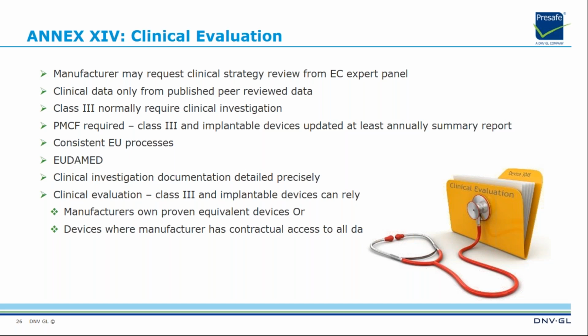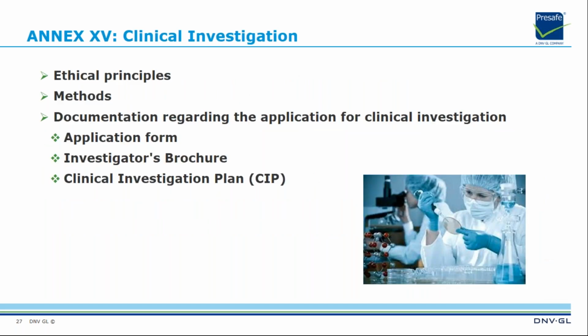evaluation reports, if not reviewed within the last 1 or 2 years, and ensure that clinical evaluation reports include post-marketing surveillance data. So PMS data must be input of clinical evaluation, especially where devices are new to market and where clinical data was limited at the time of first CE marking.